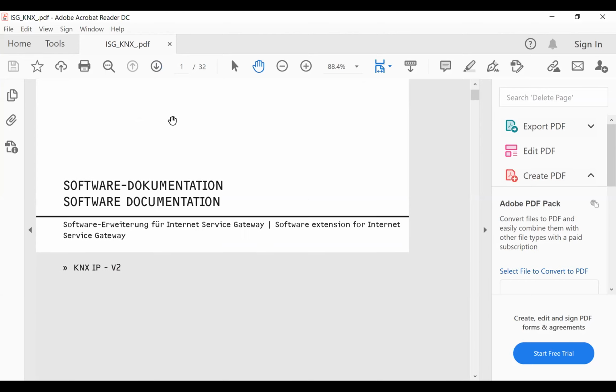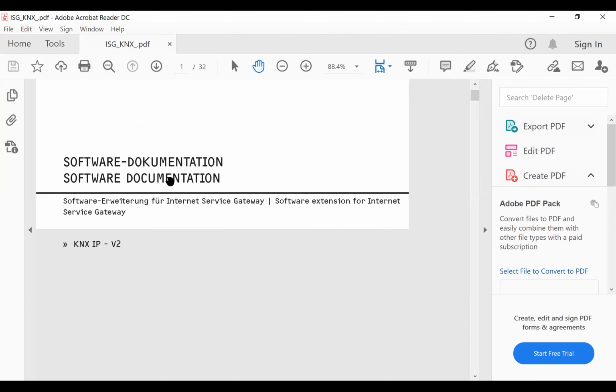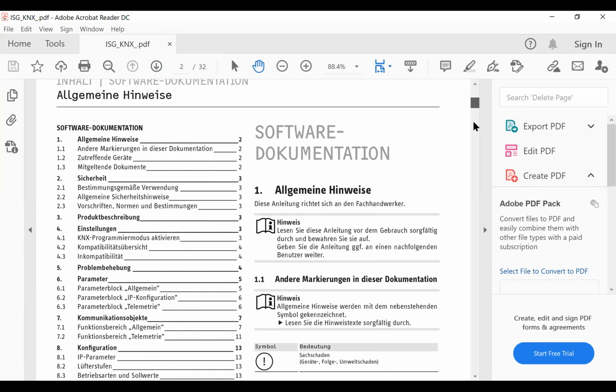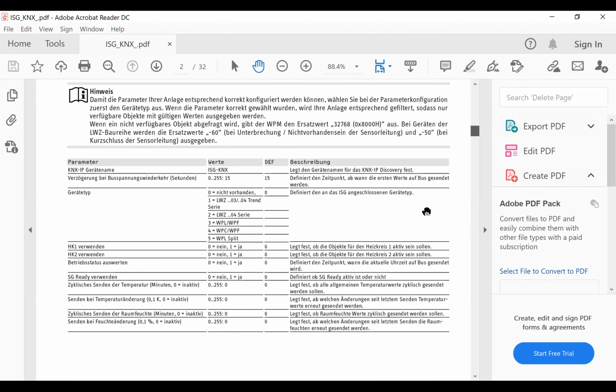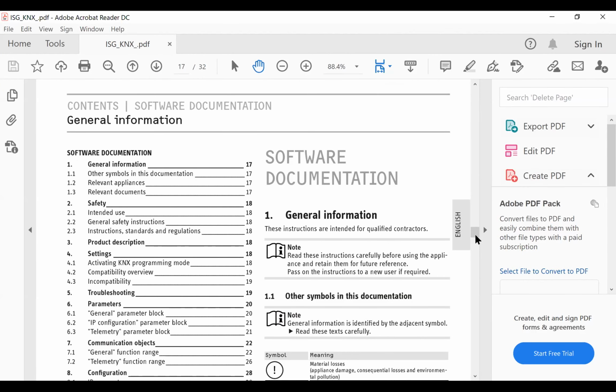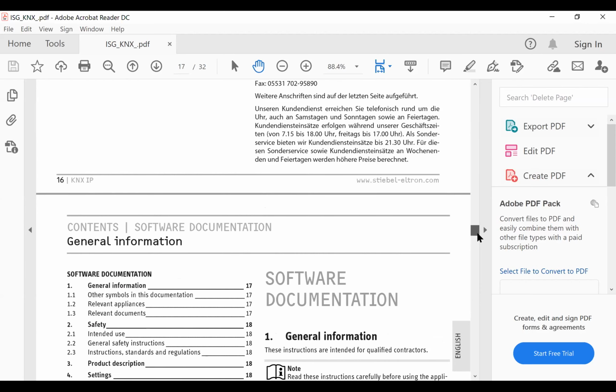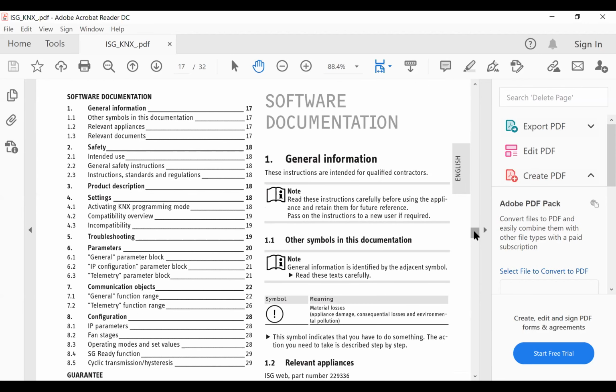Is BMS control. Okay, so what I'm showing in this document here is our KNX BMS control. KNX is a language that is transmitting data to and from our WPM. So we can, via our ISG, which is our Internet Service Gateway. So our ISG is obviously connecting our heat pump manager to the network. We can integrate with somebody's BMS system that they're putting in their building. And we can talk to it through a chosen language. So we can do Modbus and we can do KNX.